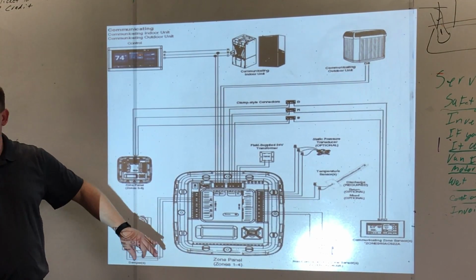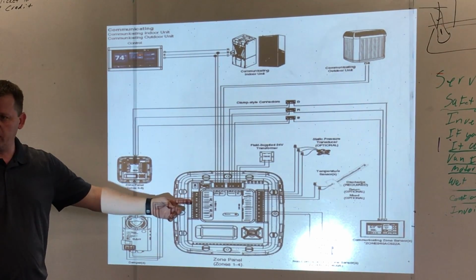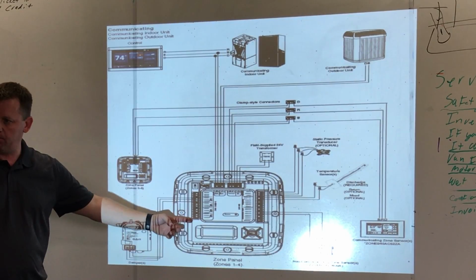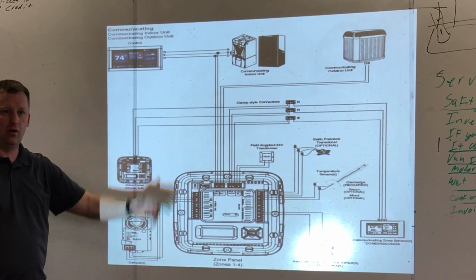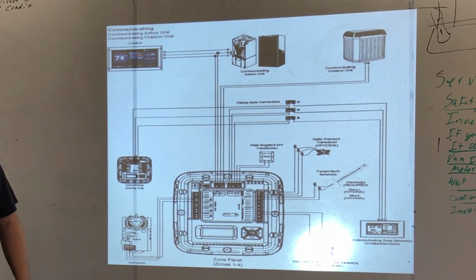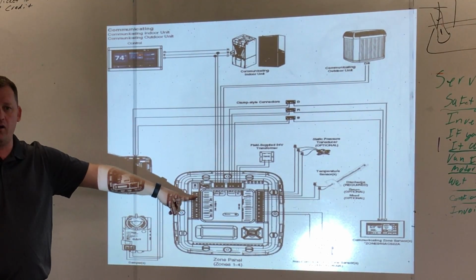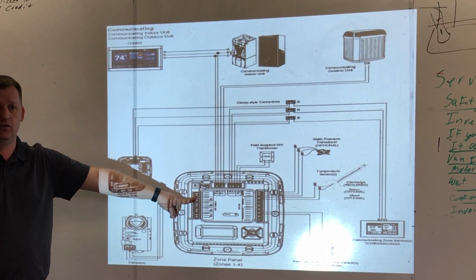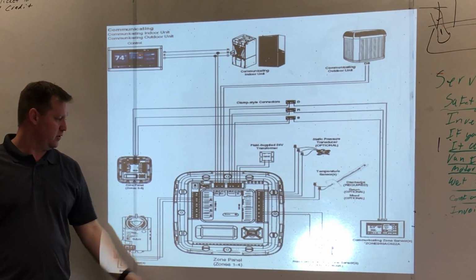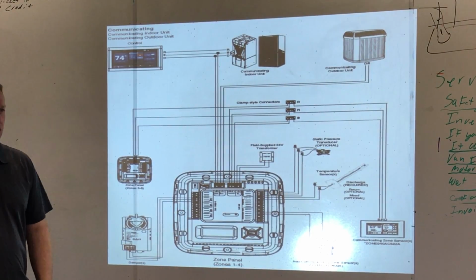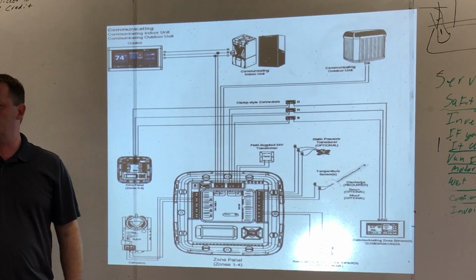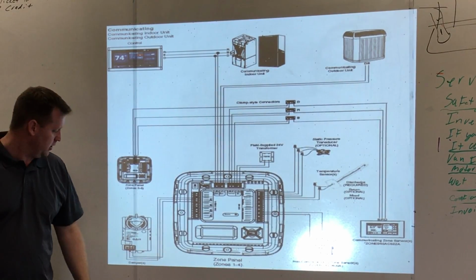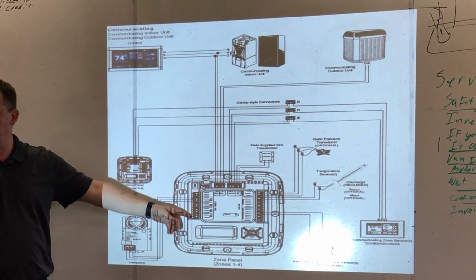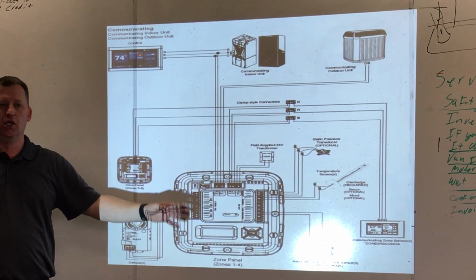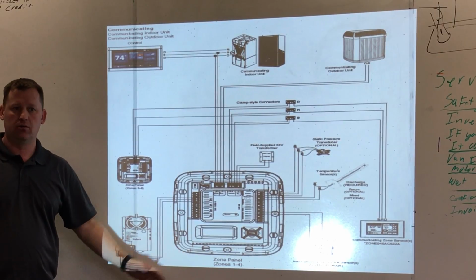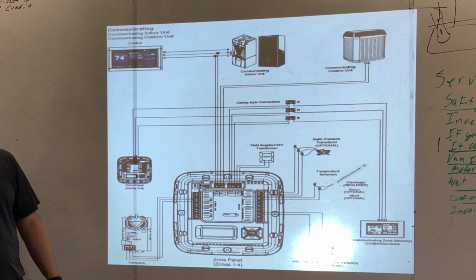The other thing is I run into situations where guys use red, blue, green, yellow, orange, green, black, red, green, blue — that's fun for the next guy. Not only that, but if they do that, I guarantee you they've got a wiring mistake. Every time I walk in on a startup and see that, I make them change it. I don't care what colors you use — red, white, blue, or red, white, green — just do it all the same, because it eliminates problems and makes troubleshooting easier later on.